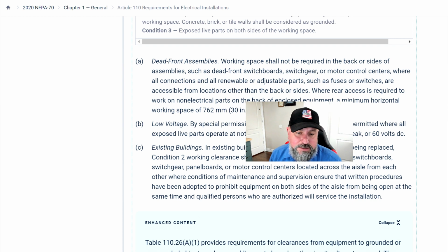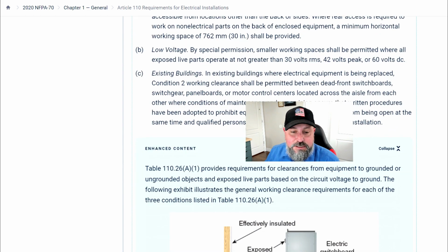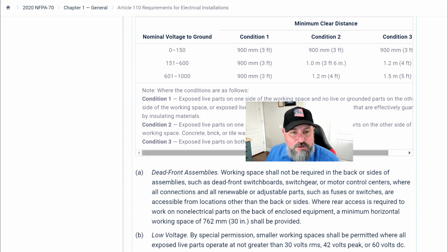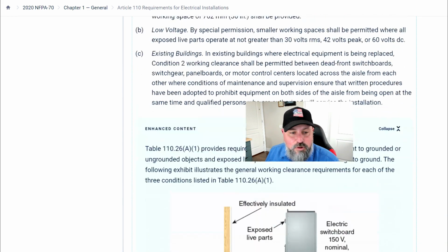Existing buildings. In existing buildings where electrical equipment is being replaced, condition 2 working clearance shall be permitted between dead front switchboards, switchgear, panelboards, or motor control centers located across the aisle from each other, where conditions of maintenance and supervision ensure that written procedures have been adopted to prohibit equipment on both sides of the aisle from being open at the same time, and qualified persons. So that's actually a stipulation I wanted to go over, and we'll go over that coming up here.